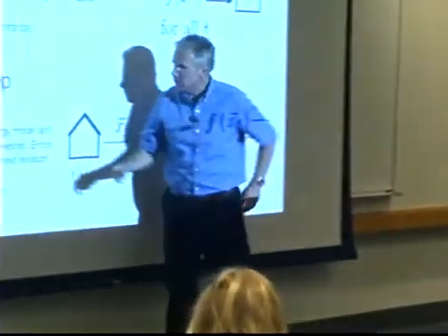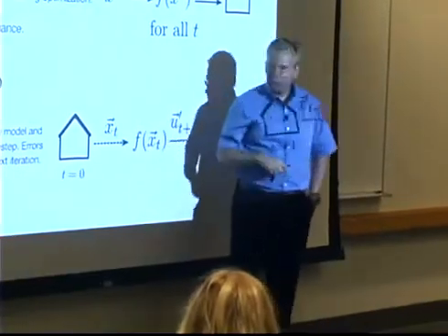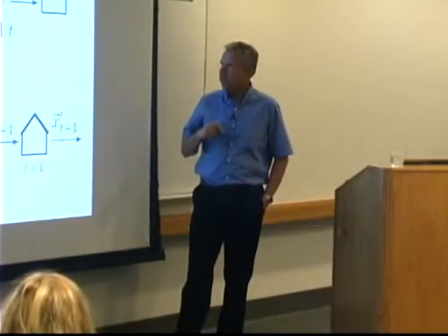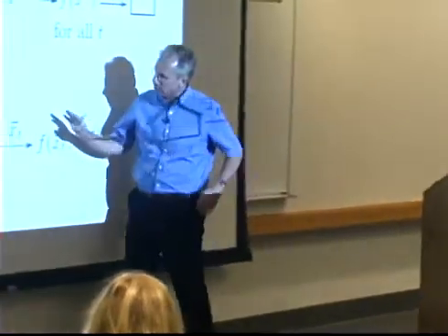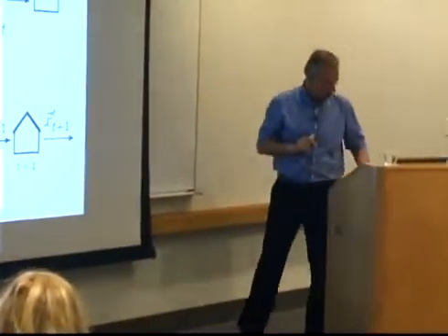The rule extraction, and in the interest of time, I'd like to take a step forward here. We test in an open loop and a closed loop fashion. Open loop is the best possible performance, where we basically predict the control vector in advance and the states are present during the optimization. In a closed loop fashion, we embed the rule in the energy model and evaluate it every time step so that states change and errors that we have may feed forward into the simulation. They may impact the next iteration. That's a much more real-world performance. So the closed loop analysis of our rules is a more realistic assessment of the quality of our rules.